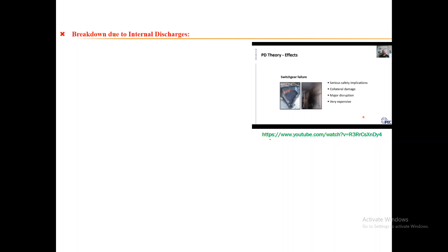On the switchgear side of things then, this is quite a dramatic picture. On the wall here, this is actually compound from the cable termination. So this is a compound filled cable termination. This is from London, a picture we took in London. This is the opposite wall, so it's not carbonization from a large fire or something, even though it looks like that.